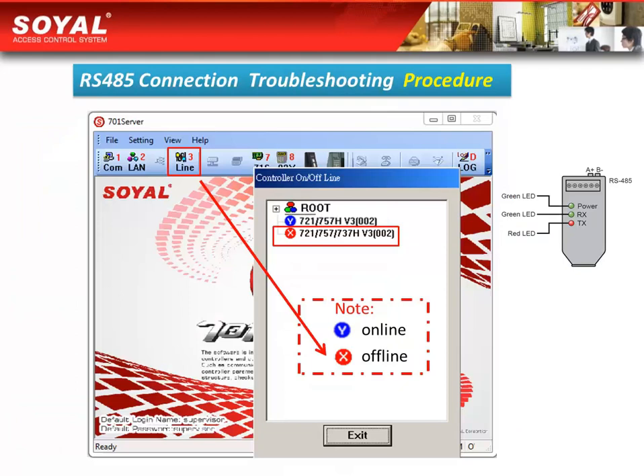This picture shows you how to distinguish whether your RS485 connection is successful or not. First, go to the 701 server and click the line item. If you see the blue mark like this, it means you connected successfully. But if you see the red mark here, it means your RS485 did not connect successfully.